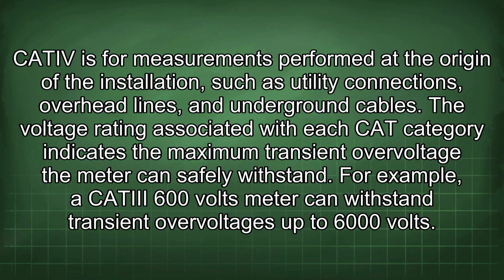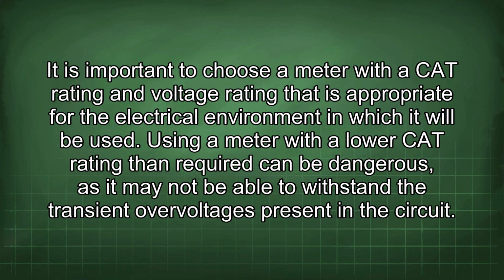The voltage rating associated with each CAT category indicates the maximum transient overvoltage the meter can safely withstand. For example, a CAT III 600 volts meter can withstand transient overvoltages up to 6000 volts. It is important to choose a meter with a CAT rating and voltage rating that is appropriate for the electrical environment in which it will be used. Using a meter with a lower CAT rating than required can be dangerous, as it may not be able to withstand the transient overvoltages present in the circuit.